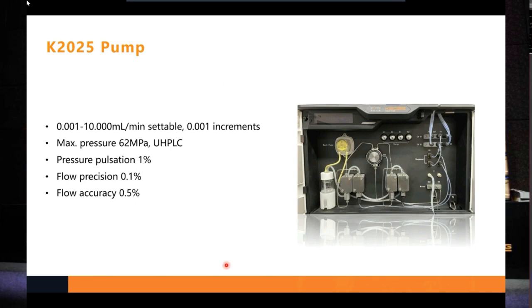Here are some basic specs of the pump. The flow range is from 0 to 10 mL per minute. The max pressure is 62 megapascals. The UHPLC performance is available for analysis, and the pressure pulsation is 1%. And the flow precision and accuracy are 0.1% and 0.5% respectively.